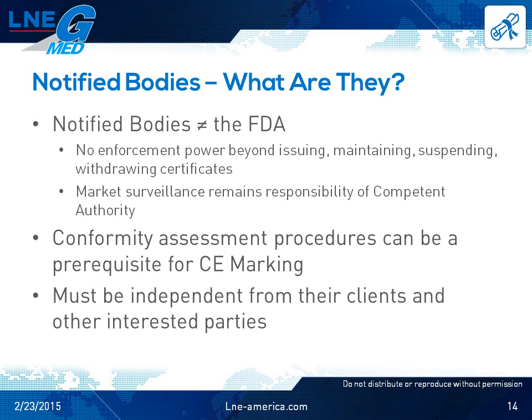Now, I should note here a common misconception that notified bodies are like the FDA in the US. We're not. Unlike the FDA, we don't really have any enforcement power beyond issuing, maintaining, suspending, and withdrawing CE certificates. And the competent authorities are the ones that handle market surveillance. So, notified bodies don't investigate manufacturers, and notified bodies can't order recalls or pull devices off the market.